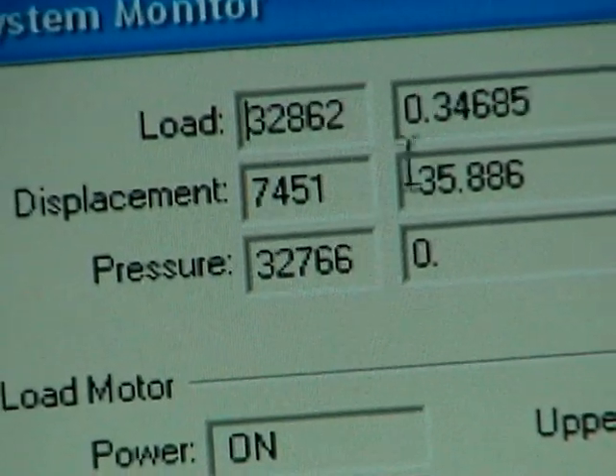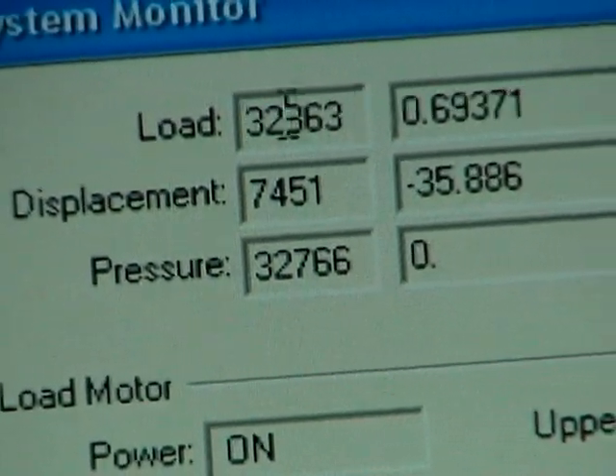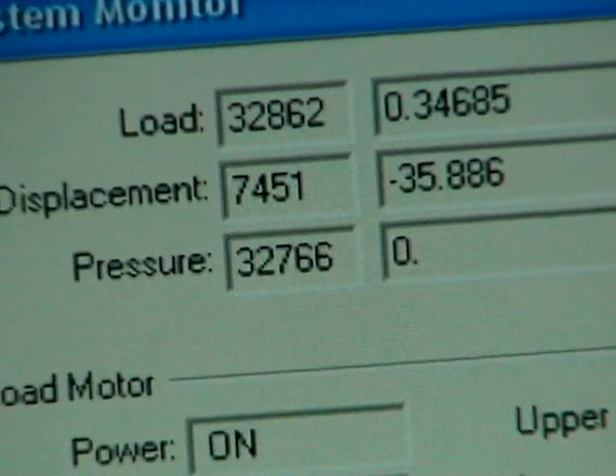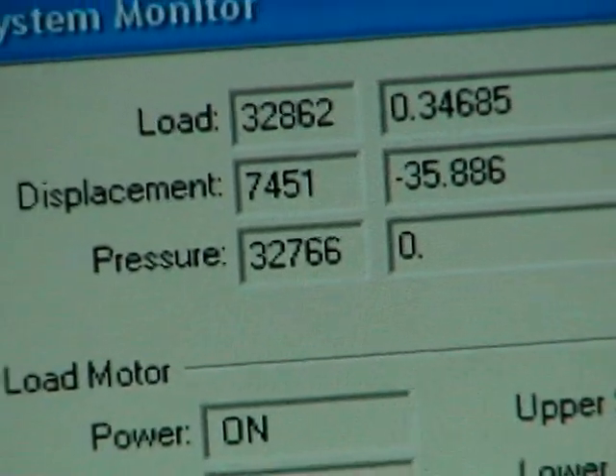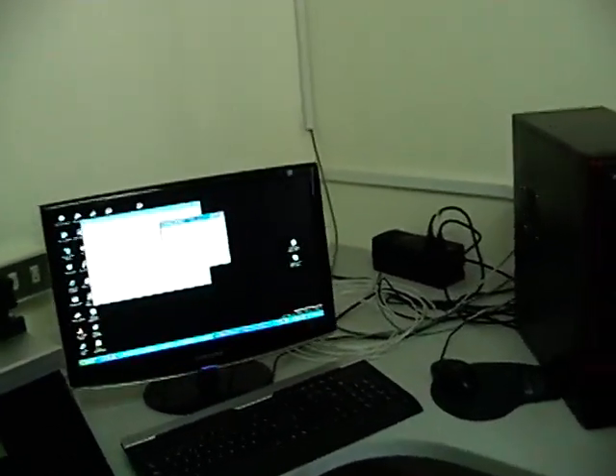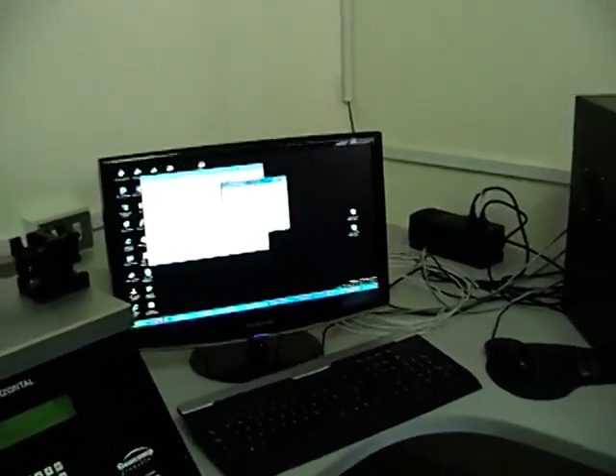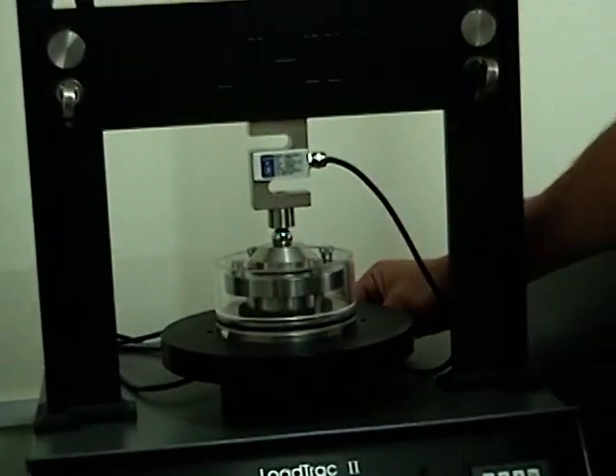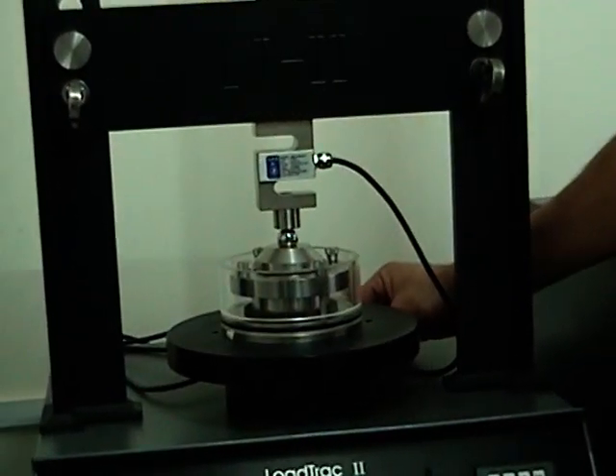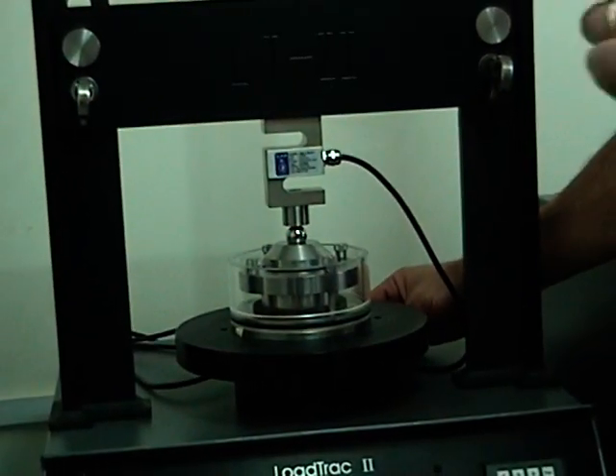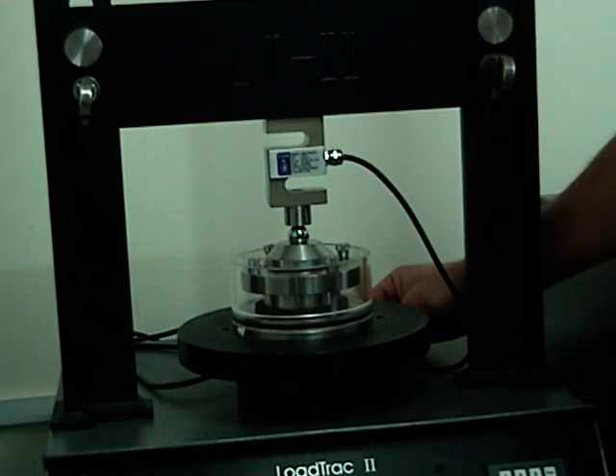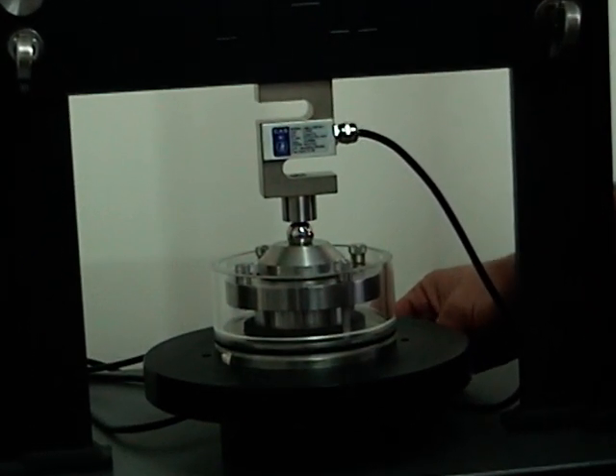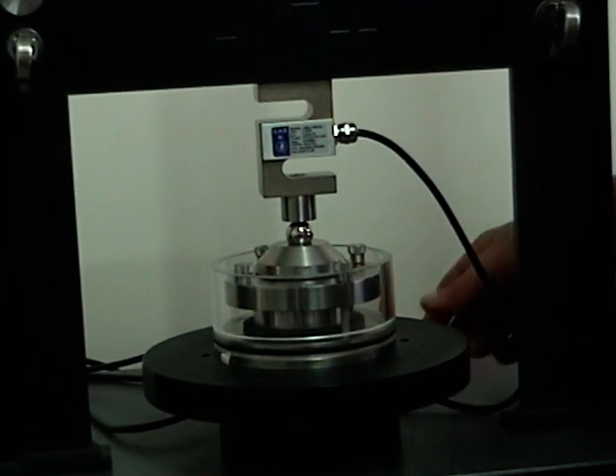We have load, we have displacement. The load here is showing almost zero. If we press on the load cell as hard as we can, we should see about 100 Newton. And again, the displacement that is underneath the platen, if we move it down, we should see displacement. We can put a gauge, a feeler gauge, and we can see that the movement corresponds to the thickness of the feeler gauge.